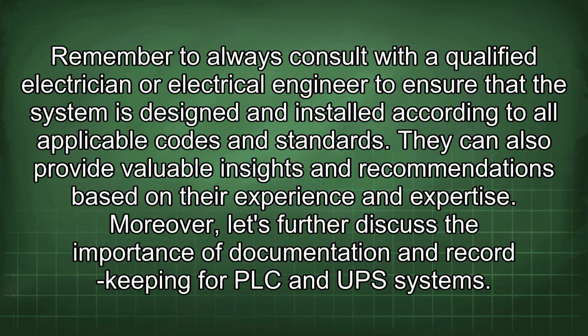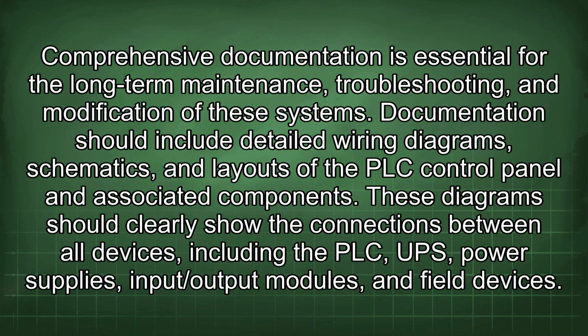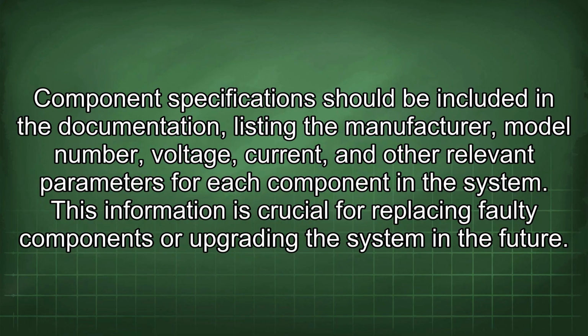Moreover, let's further discuss the importance of documentation and record keeping for PLC and UPS systems. Comprehensive documentation is essential for the long-term maintenance, troubleshooting, and modification of these systems. Documentation should include detailed wiring diagrams, schematics, and layouts of the PLC control panel and associated components. These diagrams should clearly show the connections between all devices, including the PLC, UPS, power supplies, input/output modules, and field devices. Component specifications should be included in the documentation, listing the manufacturer, model number, voltage, current, and other relevant parameters for each component in the system. This information is crucial for replacing faulty components or upgrading the system in the future.